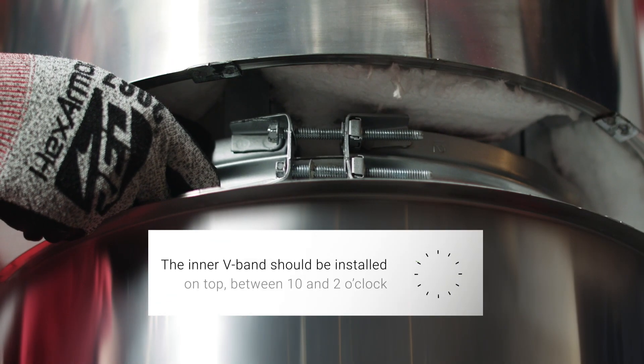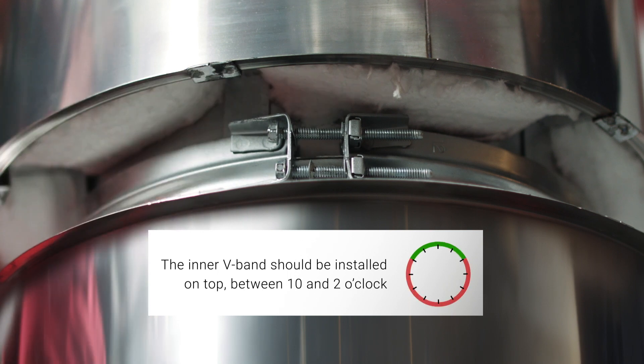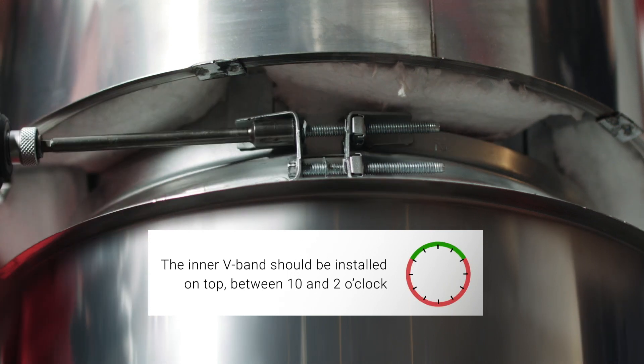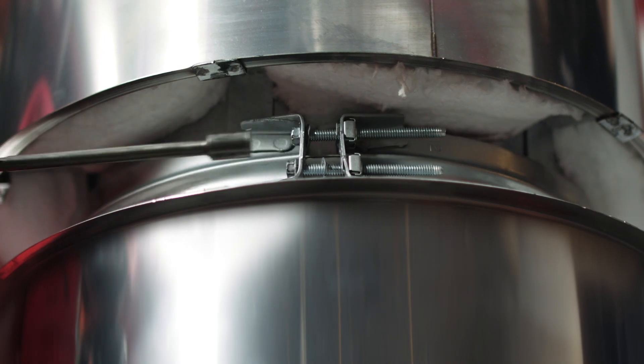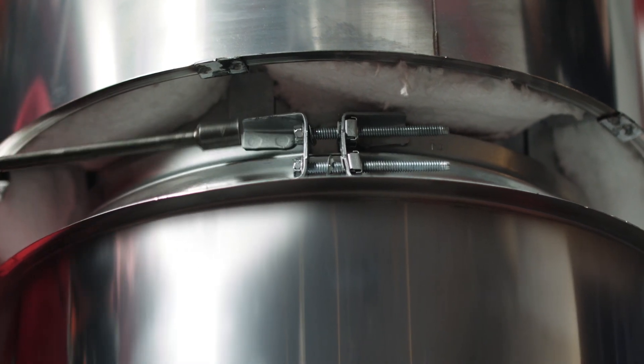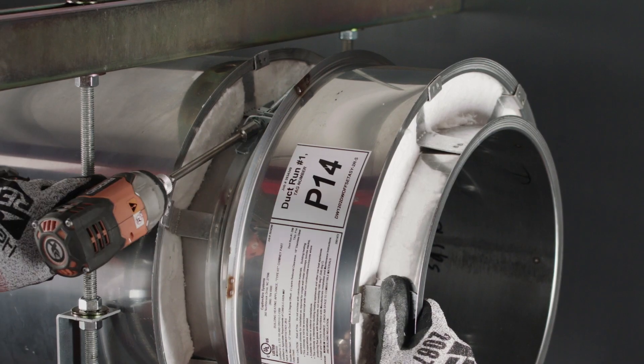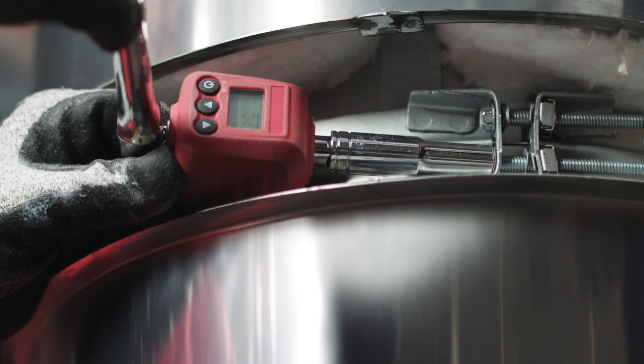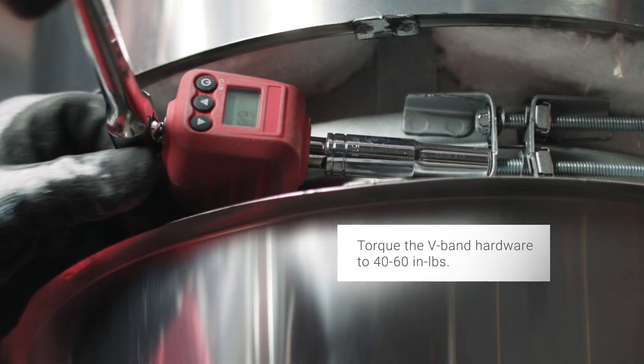For horizontal duct runs, the V-band hardware should be located on the top side of the duct between 10 and 2 o'clock. Alternate between the two bolts as you tighten. The final torque should be between 40 and 60 inch-pounds.